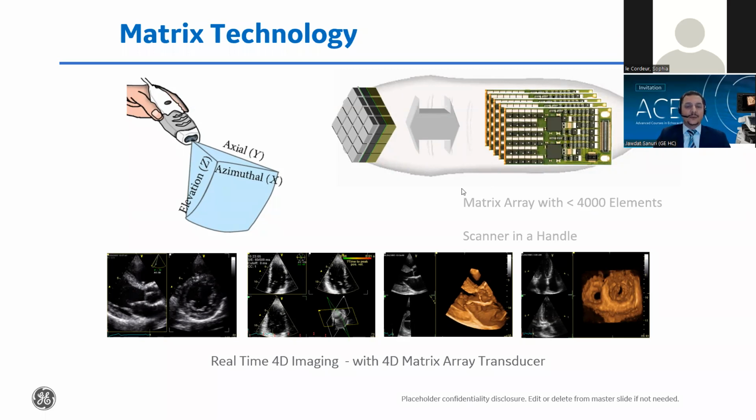This is why the early probes used to be very bulky, because they used to have somewhere in the vicinity of 6 or 8 multi-layer circuit boards, in order to be able to do a little bit of the multiplexing in terms of electronics, as we call it, that will enable us to process this much data coming from this huge number of elements on the probes.